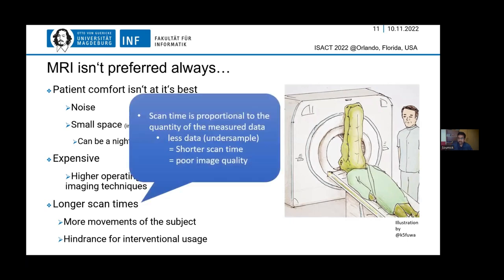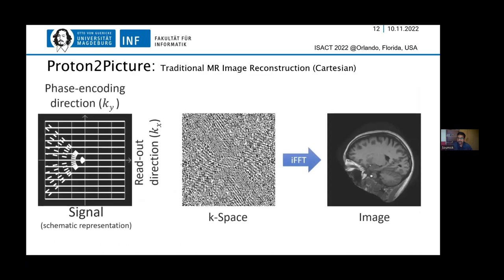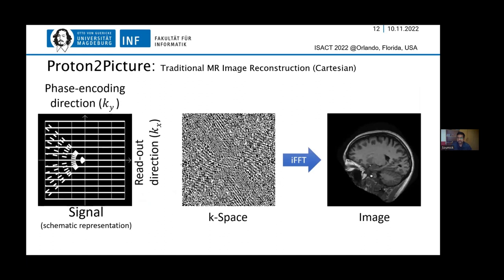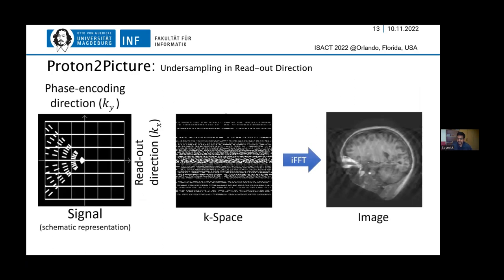This longer scan time is exactly what I worked on. The scan time is proportional to the amount of data we are measuring, so if we acquire less data, we will be faster — but then image quality would also be poorer. In MRI, data is not acquired directly in image space, but in frequency space or k-space, and we apply an inverse fast Fourier transform to get the image. To make it faster, if we ignore parts of the data, we have undersampling, but we end up with artifacts.